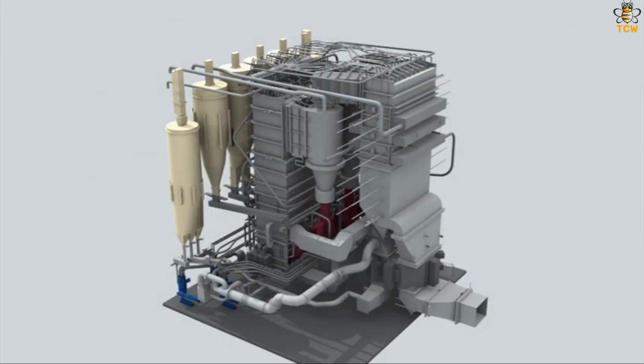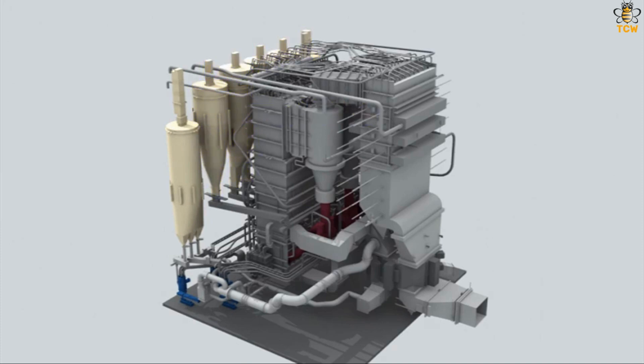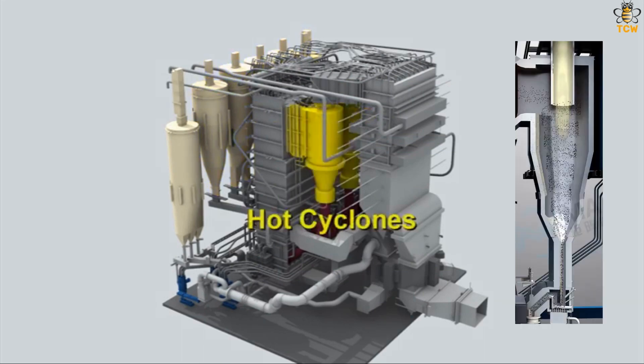The main components of the boiler at a power plant include fuel silos and hot cyclones. Fuel silos are coal fuel storage containers where coal will be channeled to the bottom of the boiler to be burned. A hot cyclone is a device to remove particulates from hot gas from coal combustion, not through a filtration mechanism, but through a vortex separation mechanism.